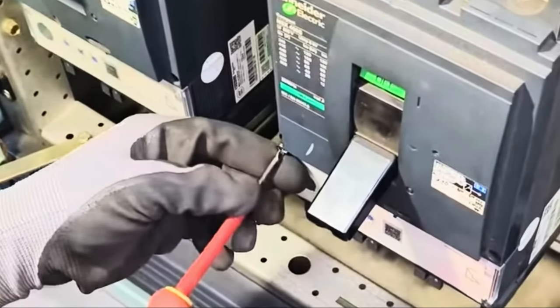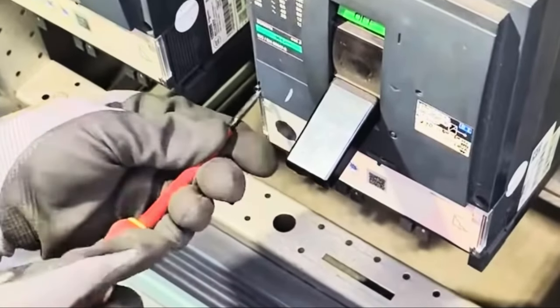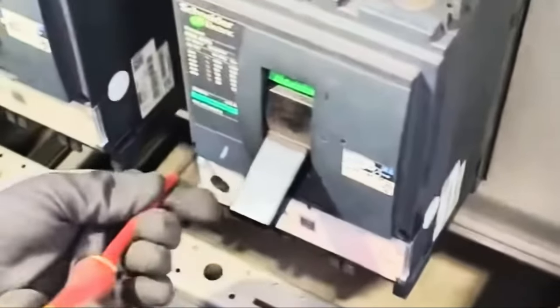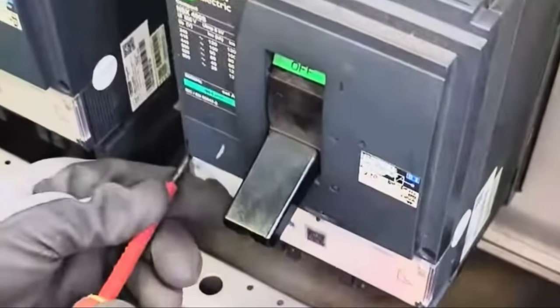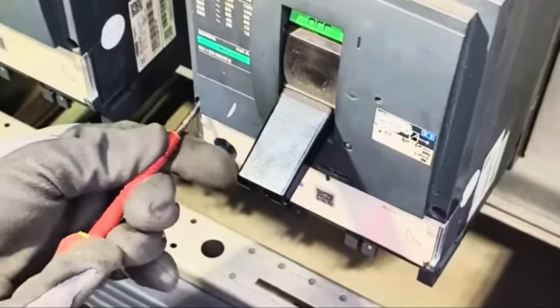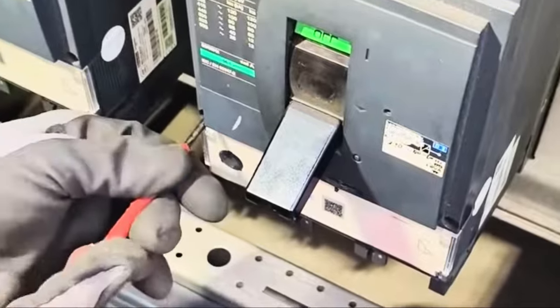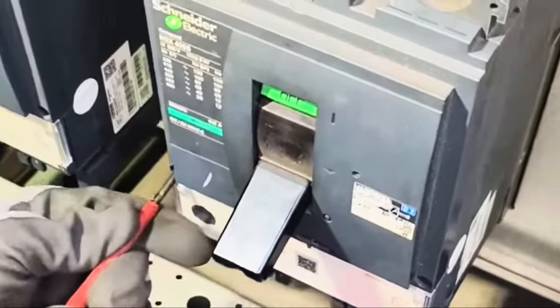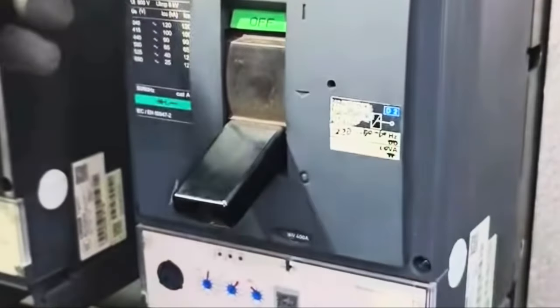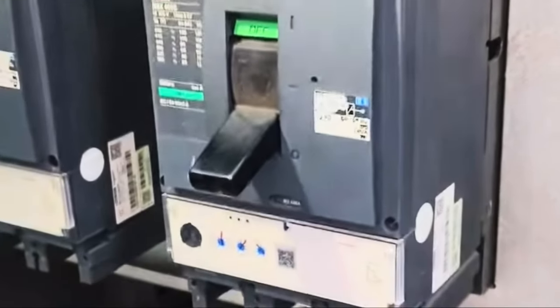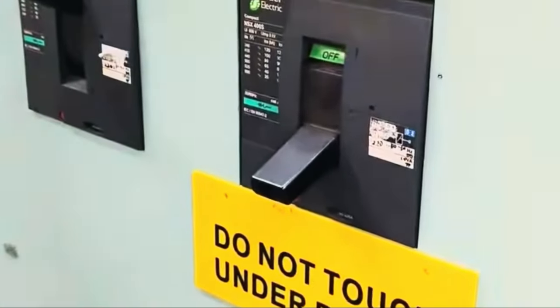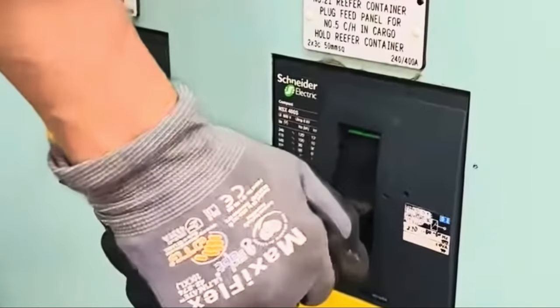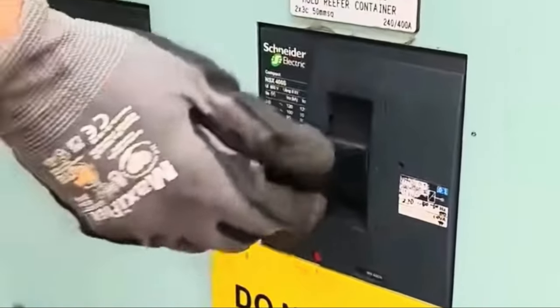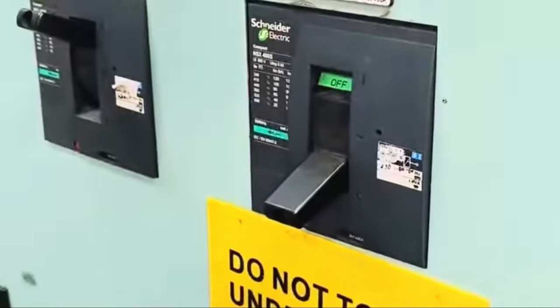After completing the work, you should cover the front panel properly and check that there is no loose connection or loose screw, so the MCCB keeps functioning normally. So always ensure all connections and all screws are properly tightened. Now, after tightening the connections, we will check whether it is working or not. Now we check all the connections inside, and all are found okay.